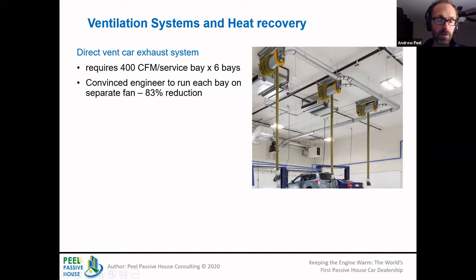But then there was an issue with drawing updates and communication with the contractor. They ended up installing and connecting three of the fans together, so we end up with two fans instead of six. So we end up increasing the heat loss again, based on how it was constructed. And luckily we could still manage that within our heat balance.